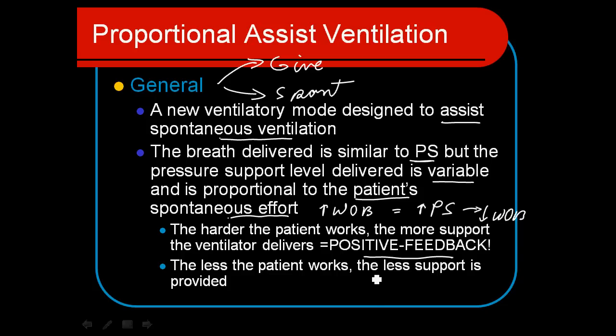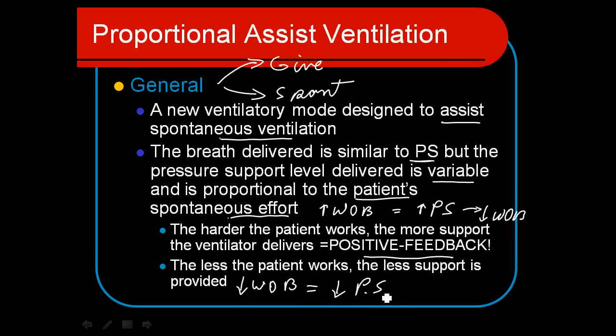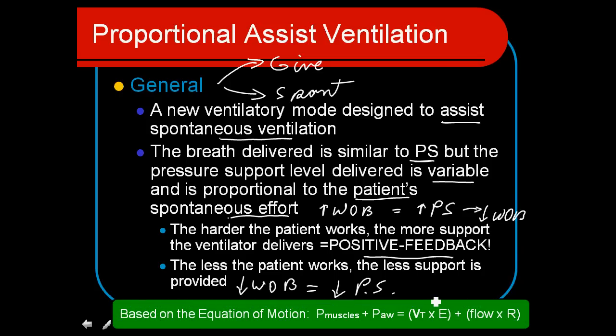The less the patient works, the less support is provided. So if the patient is relaxed and comfortably breathing, getting good tidal volumes, the ventilator is smart enough to realize that their work of breathing is very, very low, so they don't require very much pressure support. It's a positive feedback system in that the more you work, the more support you get. That's actually different than volume control, and it's much more intelligent. I think this mode has a lot of promise.